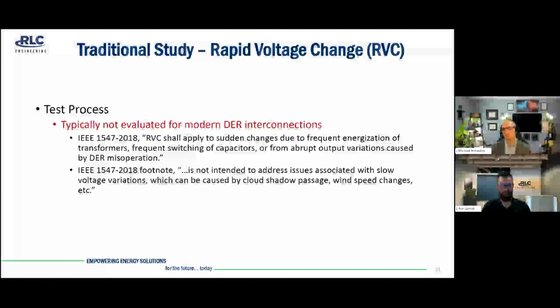It is not intended to address issues associated with slow voltage variations, which can be caused by cloud shadow passage and wind speed changes. Oftentimes, if we're reviewing a third-party system impact study and RVC is included, it's usually included to assess things like these slow voltage variations, which is not technically the intent of rapid voltage change. So that's kind of an important consideration. And where it's most important is when you're considering mitigations. There's a lot more mitigation options for alleviating or ameliorating the slow voltage variations versus the rapid voltage change, which usually happens over a 1 second period.